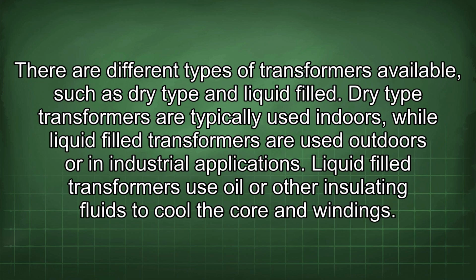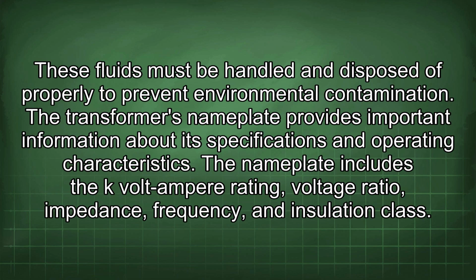There are different types of transformers available, such as dry-type and liquid-filled. Dry-type transformers are typically used indoors, while liquid-filled transformers are used outdoors or in industrial applications. Liquid-filled transformers use oil or other insulating fluids to cool the core and windings. These fluids must be handled and disposed of properly to prevent environmental contamination.